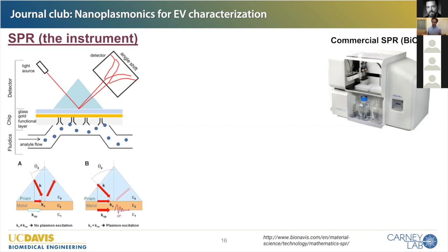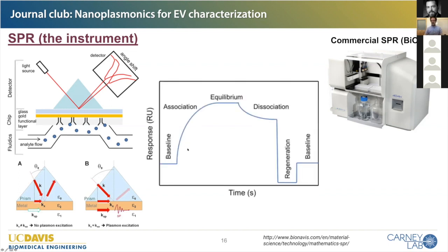Now, if a biomass binds to the other side of this, like you can see an antibody-coated bottom side with a microfluidic channel over, the biomass changes, the refractive index changes, and the angle that you absorb changes. So very subtle shifts in angle of peak absorption can give you very small biomass increments of binding. And people have used this in cool microfluidic experiments to measure all kinds of kinetic and thermodynamic properties of binding.